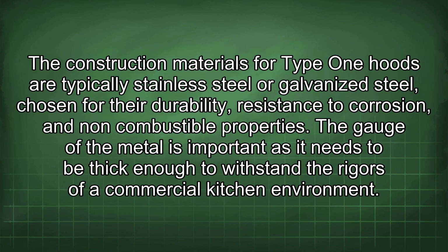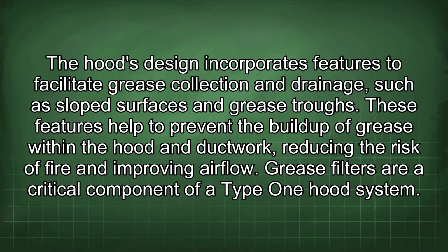The construction materials for Type 1 hoods are typically stainless steel or galvanized steel, chosen for their durability, resistance to corrosion, and non-combustible properties. The gauge of the metal is important as it needs to be thick enough to withstand the rigors of a commercial kitchen environment. The hood's design incorporates features to facilitate grease collection and drainage, such as sloped surfaces and grease troughs. These features help to prevent the buildup of grease within the hood and ductwork, reducing the risk of fire and improving airflow. Grease filters are a critical component of a Type 1 hood system.